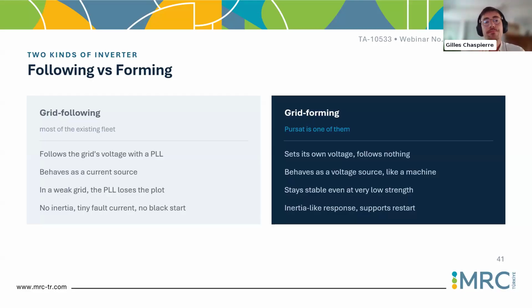Enter, of course, grid forming. First, grid forming is a completely new type of control, meaning it does not rely anymore on an external voltage source. It imposes its own voltage reference, meaning it can, in theory, be connected to a system without any synchronous generator. It will behave like a synchronous machine, as a voltage source behind an impedance. Of course, not through physics, through control. So it's really a control design that has been developed to mimic the behavior of a synchronous generator, provide inertia, provide voltage controllability, and of course, most importantly, be stable even in low system strength situations.